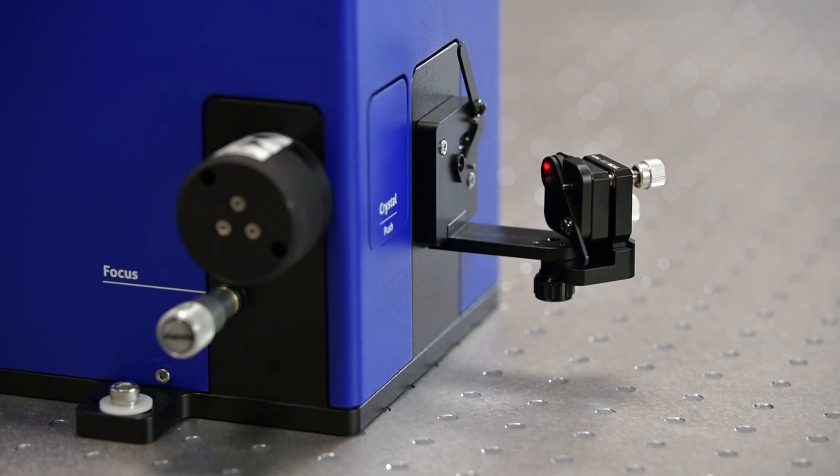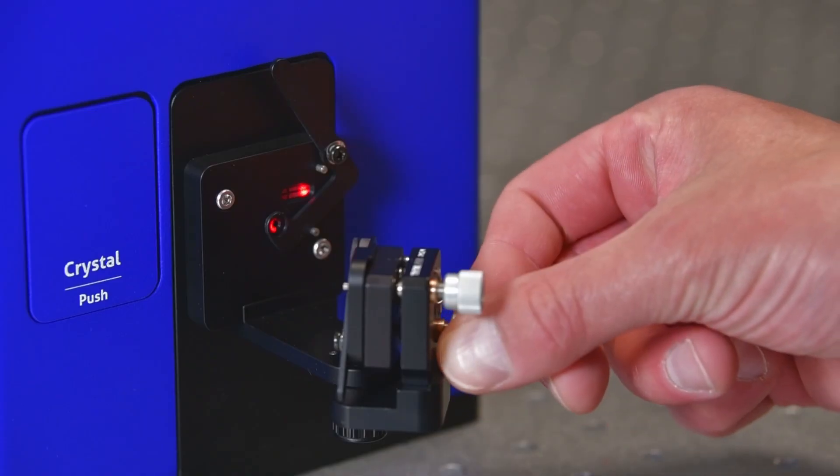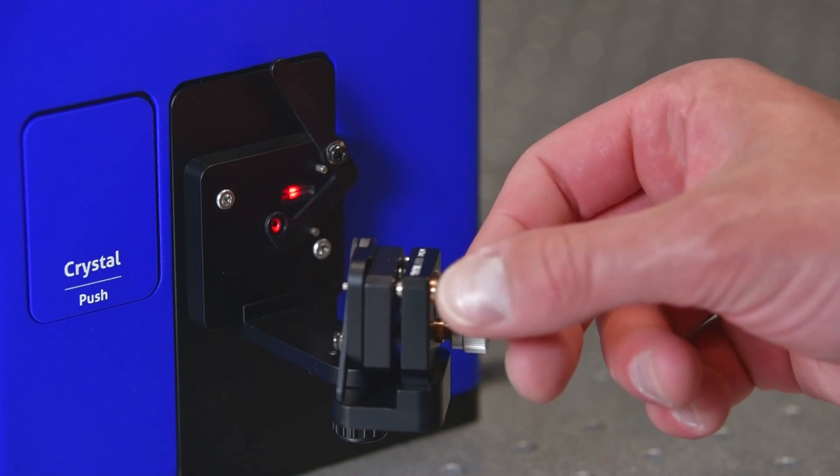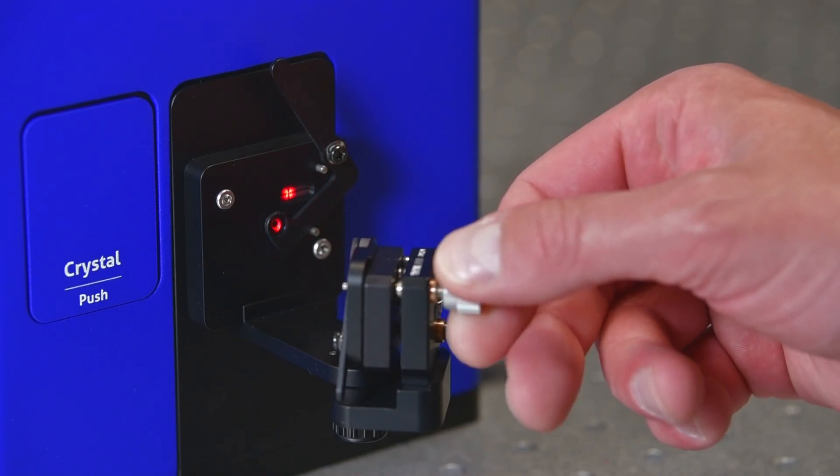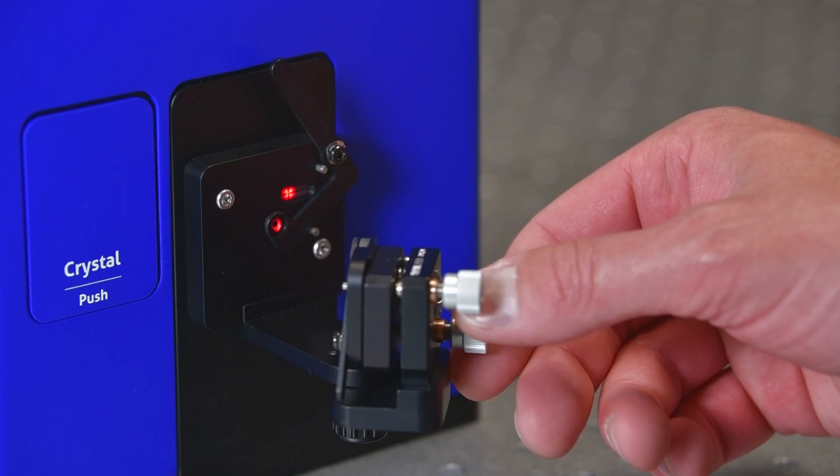With the help of the two input apertures, which are flipped down, adjust and center the beam into the input aperture. Use the screws of the input mirror to align the laser beam through the second aperture and thereafter to the crosshair.